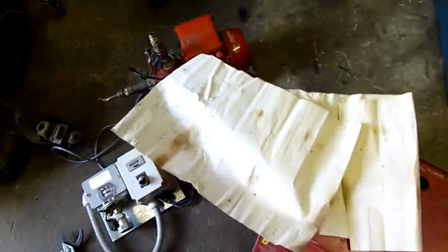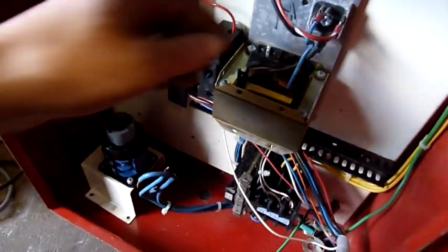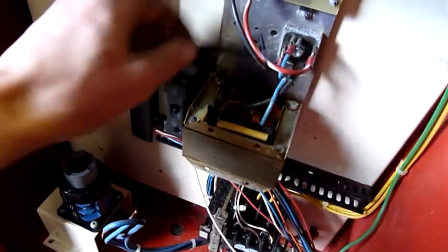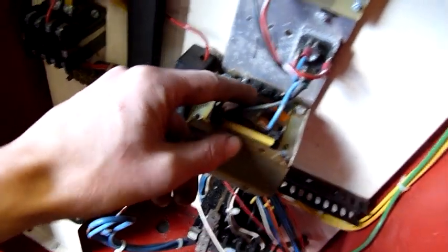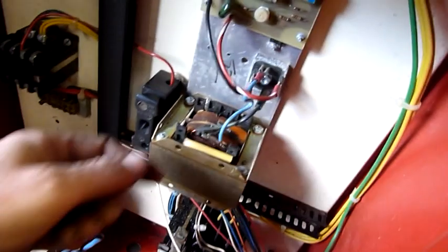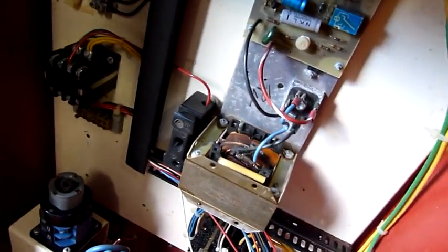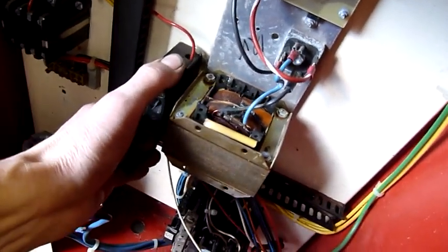Earth required on transformer — question mark. Well, that's sort of where the failures occurred. That transformer's melted down. The secondary's all loose and melted out. She's had a serious overload or short — probably a short circuit. The rectifier doesn't look too good either, so I'm wondering if the rectifier's gone short. There's a fuse on here but that's for something else. It goes through a little 8-amp contactor and it's a 10-amp ceramic fuse.